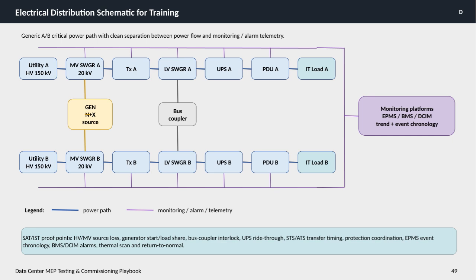Crucial proof points from SAT and IST tests include high and medium voltage source loss detection, generator start and load sharing behavior, bus coupler interlock functionality, UPS ride-through capability, transfer switch timing, protection coordination, and the accurate reporting of events and alarms by monitoring systems. Together, these elements form a comprehensive framework that supports a secure and reliable power distribution essential for data center operations.